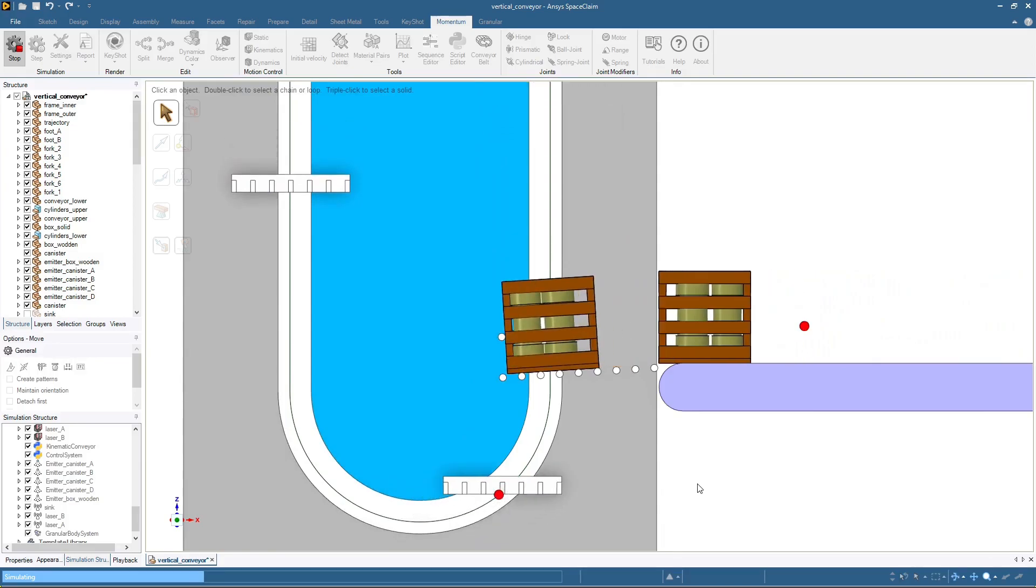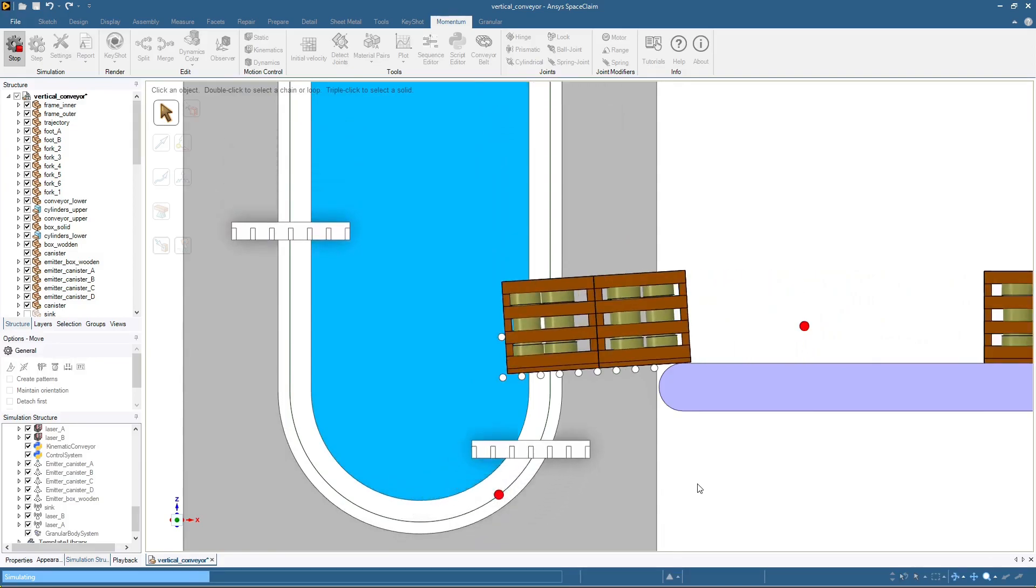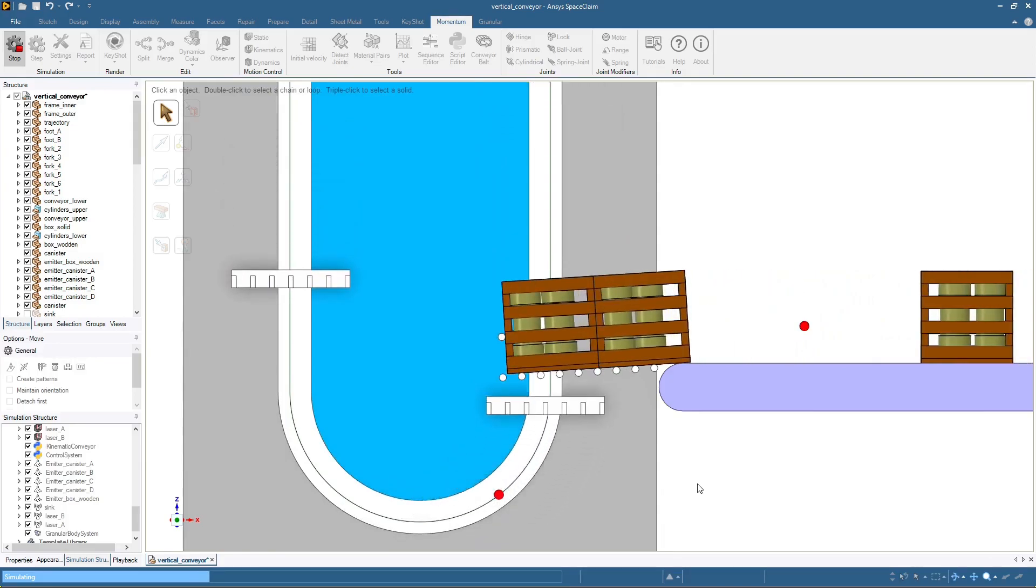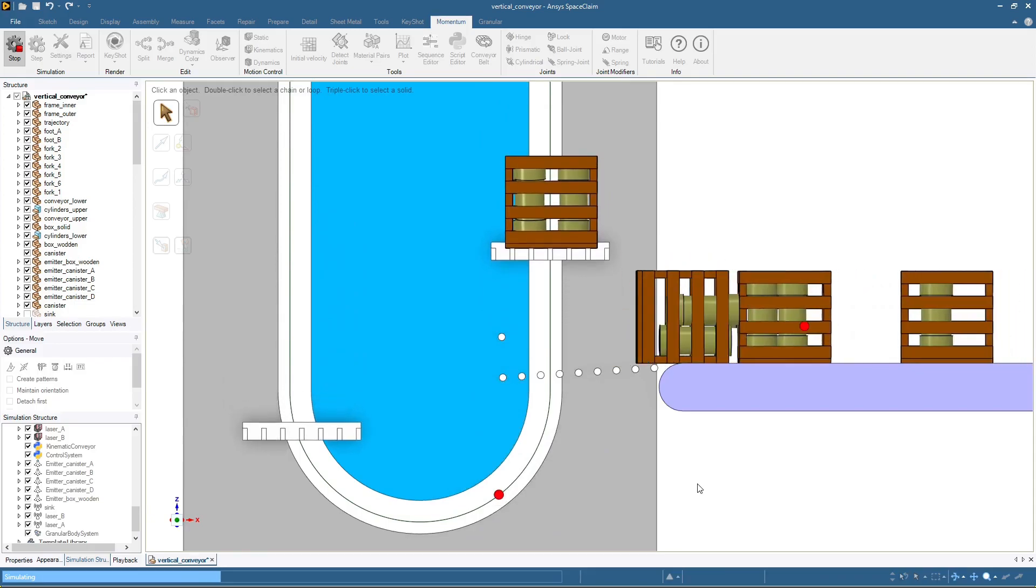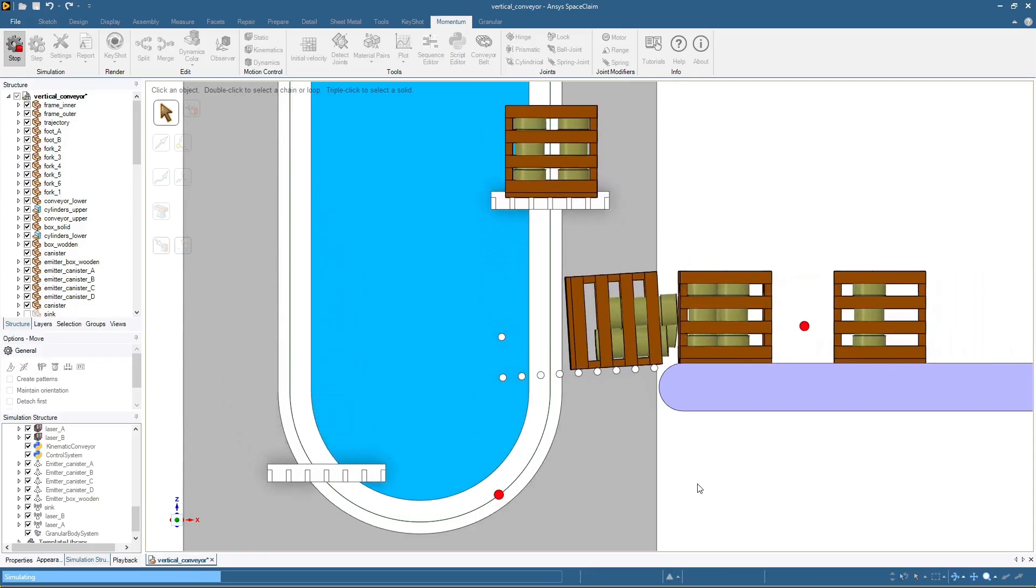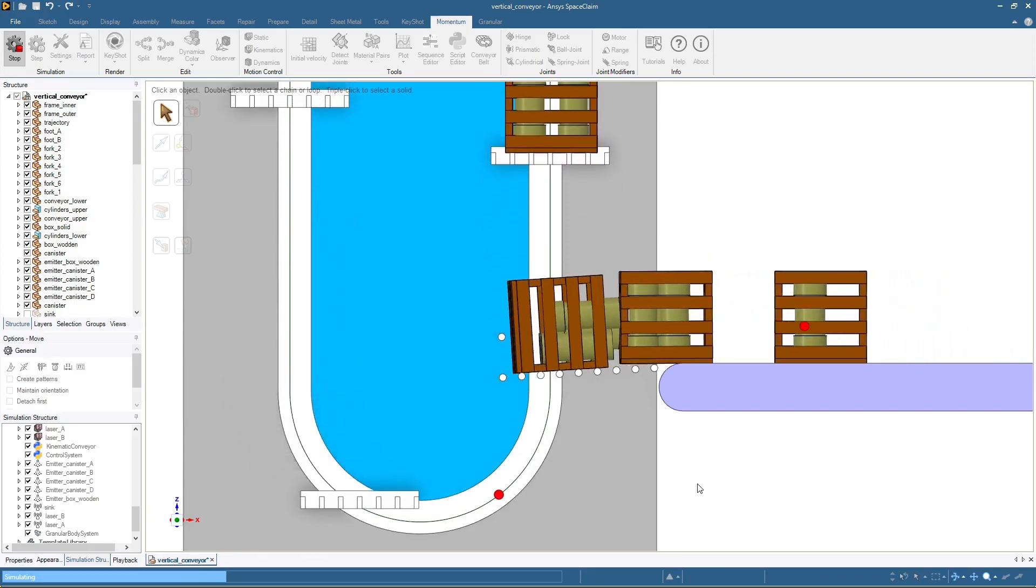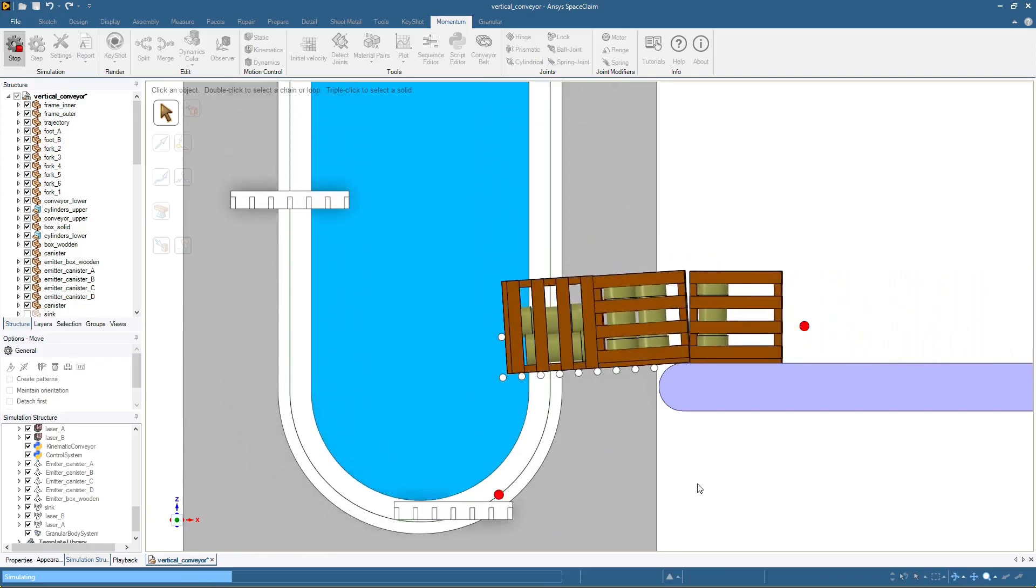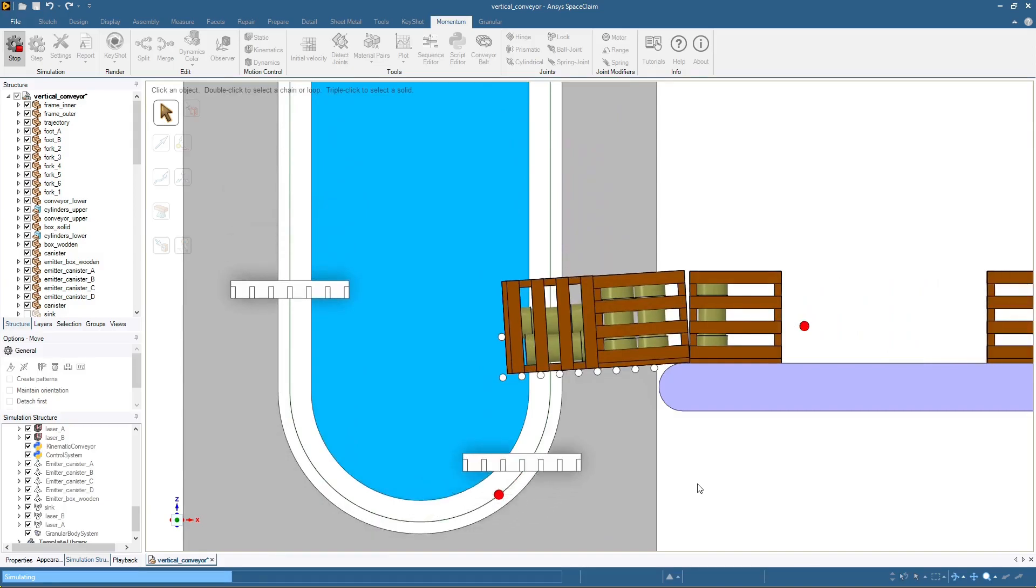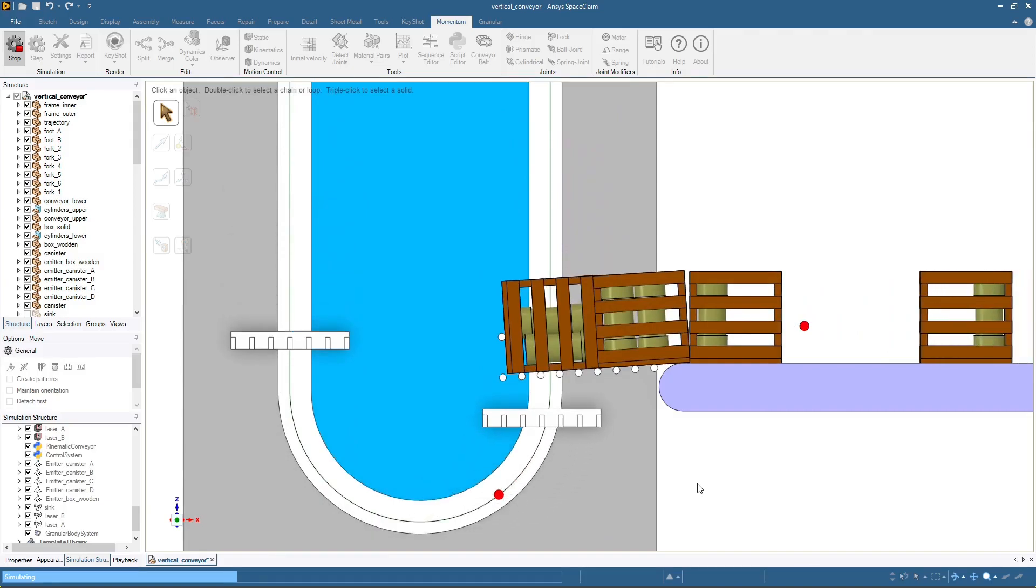What happened is that the code for our control system does not consider if the loading zone is empty or not, effectively assuming it is empty. So the second package was not stopped because if the loading zone had been empty, it would have been lifted up without problem. We need to address this.